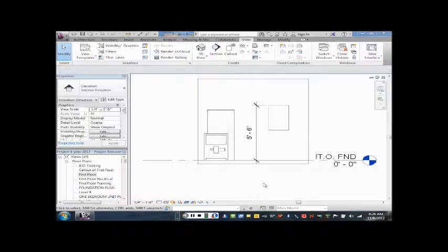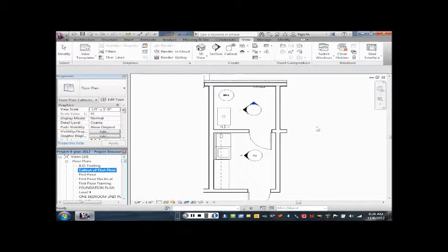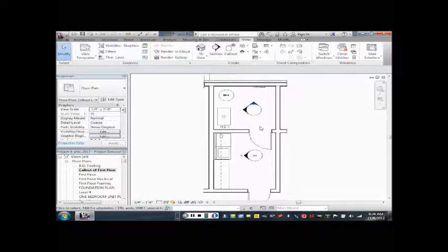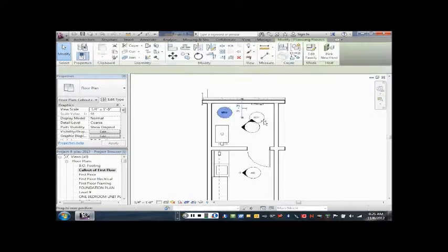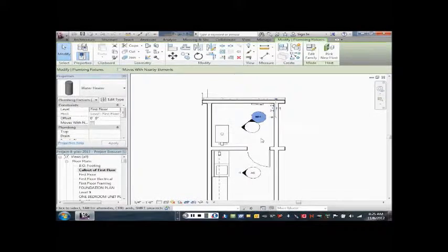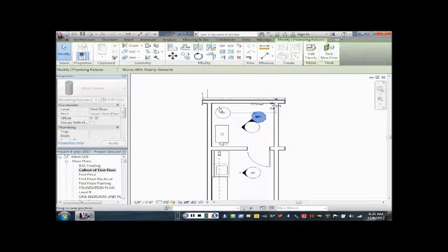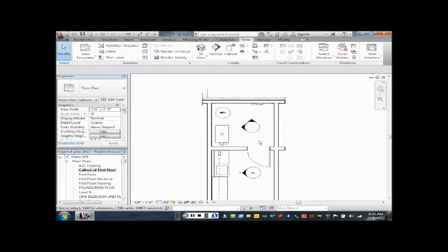Okay, so let's go back to the call out of the first floor plan again, this space. And the code requirement for the electrical panel is a minimum space directly in front of the panel of 3 feet. You have to be able to walk up to the electrical panel. So I couldn't set the water heater here, in other words, right? Because then it would be blocking that electrical panel. So in some cases, mechanical rooms are fairly tight, and that becomes a problem.